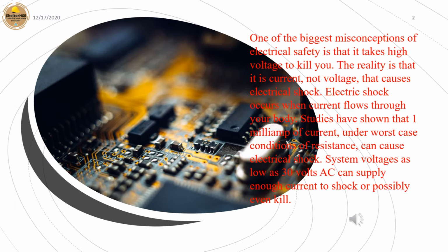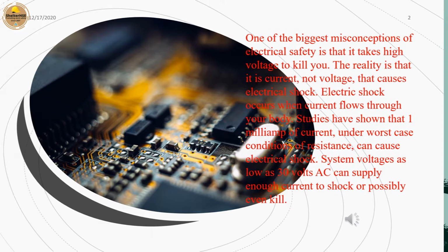One of the biggest misconceptions of electrical safety is that it takes high voltage to kill you. The reality is that it is current, not voltage, that causes electrical shock. Electric shock occurs when current flows through your body. Studies have shown that 1 milliamp of current, under worst-case conditions of resistance, can cause electrical shock. System voltages as low as 30 volts AC can supply enough current to shock or possibly even kill.